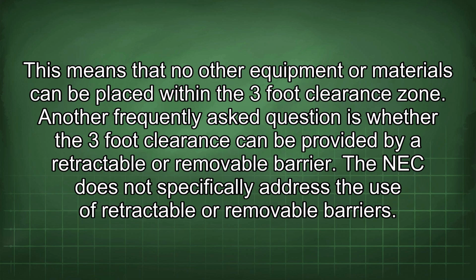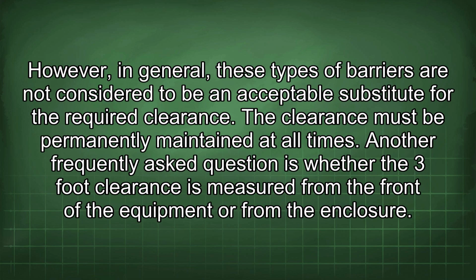Another frequently asked question is whether the 3-foot clearance can be provided by a retractable or removable barrier. The NEC does not specifically address the use of retractable or removable barriers. However, in general, these types of barriers are not considered to be an acceptable substitute for the required clearance. The clearance must be permanently maintained at all times.